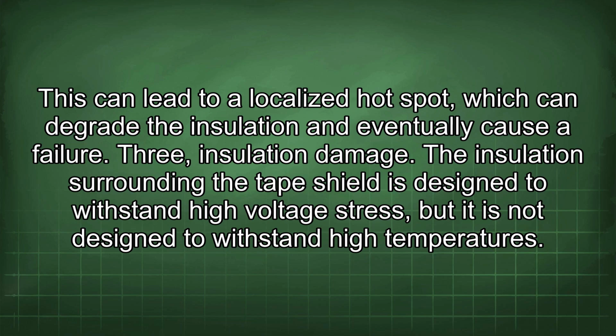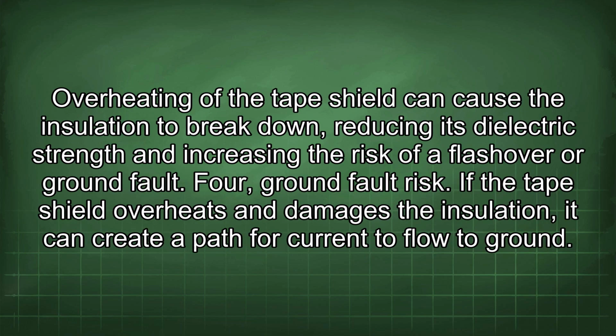3. Insulation damage. The insulation surrounding the tape shield is designed to withstand high voltage stress, but it is not designed to withstand high temperatures. Overheating of the tape shield can cause the insulation to break down, reducing its dielectric strength and increasing the risk of a flashover or ground fault.